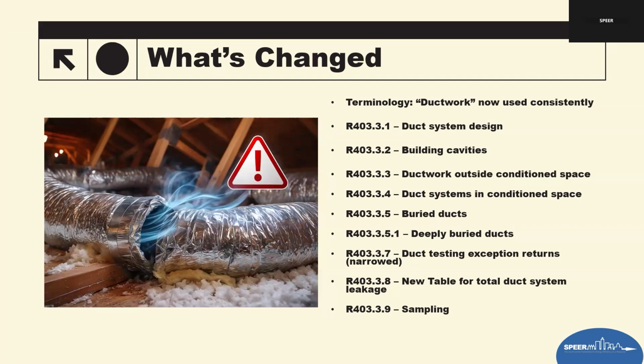And then ducts in conditioned space, where I was going with that, R403.3.4, is when you've got ducts that are now considered in the conditioned space. It's a clearer criteria. There are special rules for attics that have vapor diffusion ports. We probably won't see that in Texas. Leakage to outside must meet a specific item and section, which we'll talk about in a little bit. And then what we may or may not see in Texas is one called buried ducts. So prescriptive allowances and details are retained and clarified.